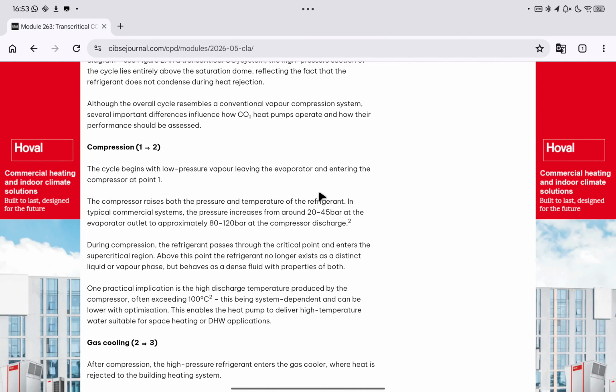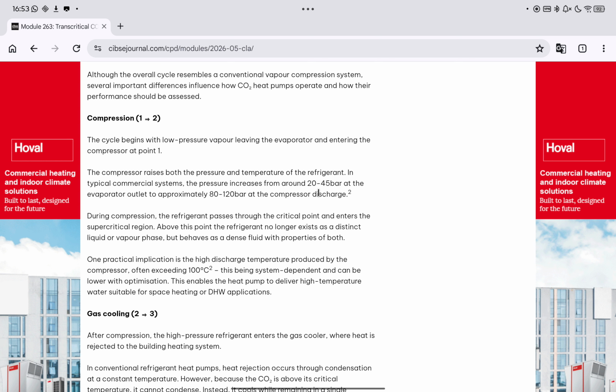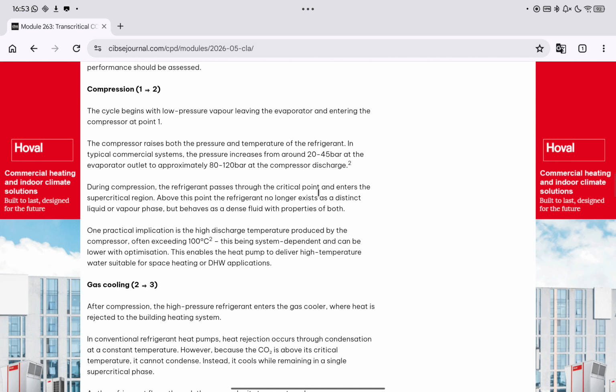One practical implication is the high discharge temperature produced by the compressor, often exceeding 100 degrees C, this being system dependent and can be lower with optimization. This enables the heat pump to deliver high temperature water suitable for space heating or domestic hot water applications.